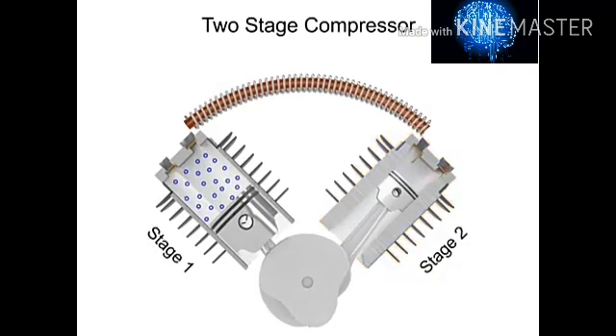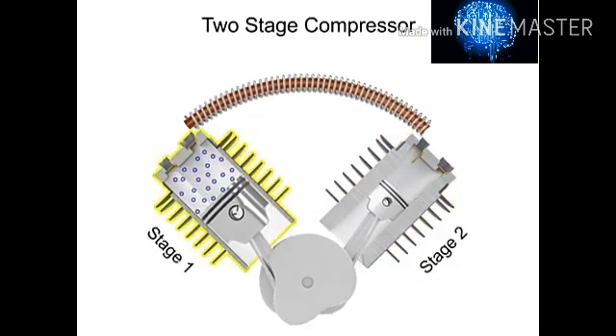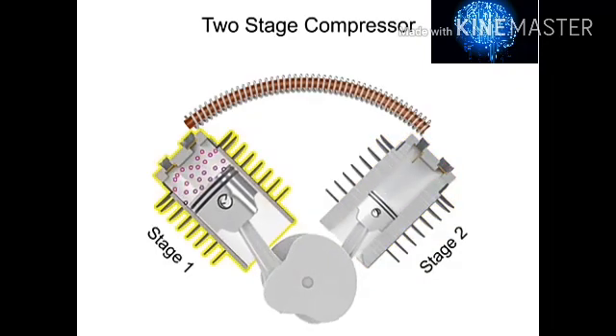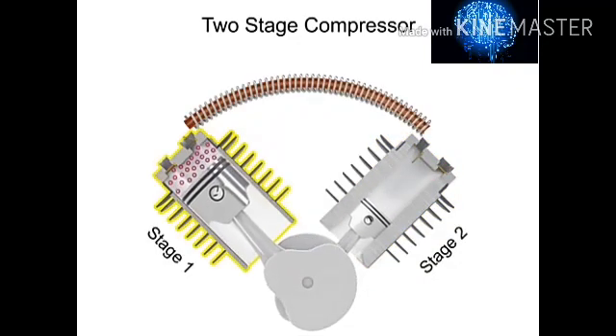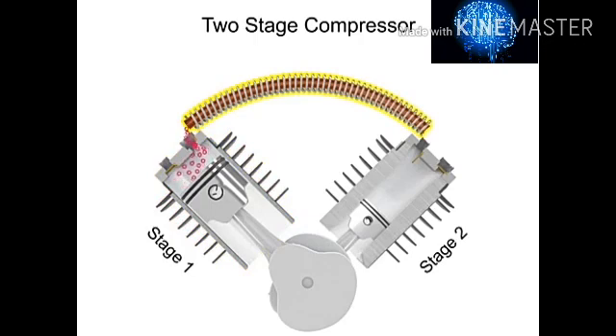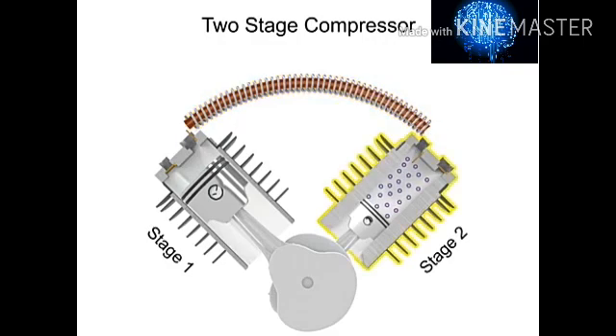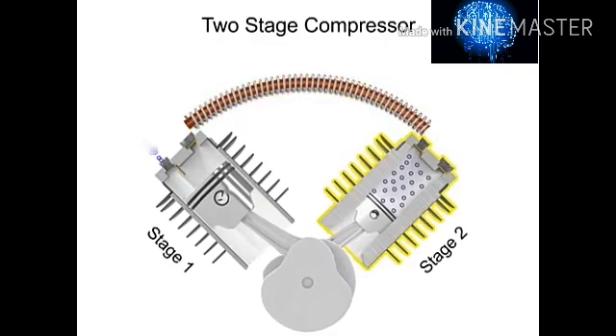The hot compressed air from the first stage is conducted to the second stage through finned tubing which is exposed to the air from a flywheel fan. After the air is cooled within the tube, the compressed air enters the second stage to be compressed even further.